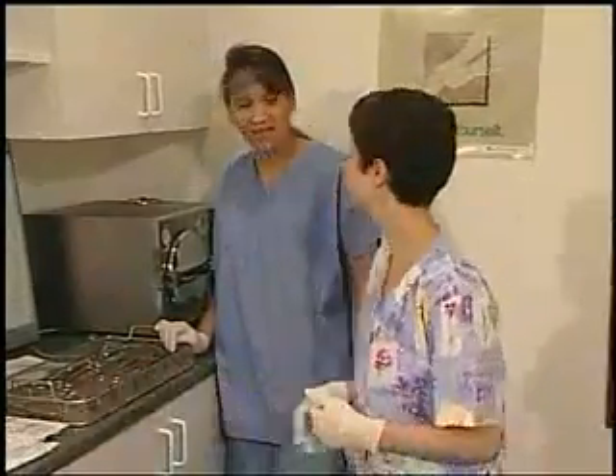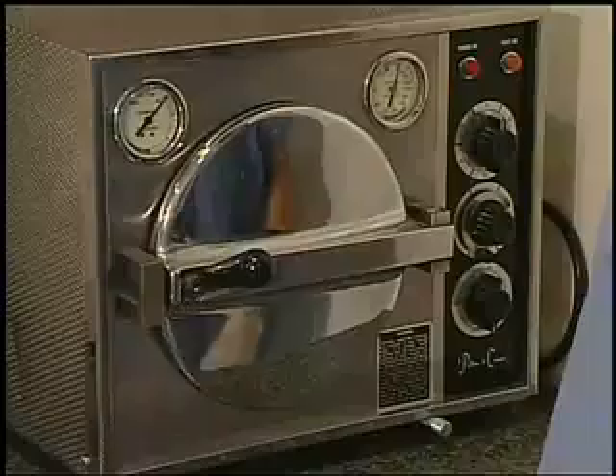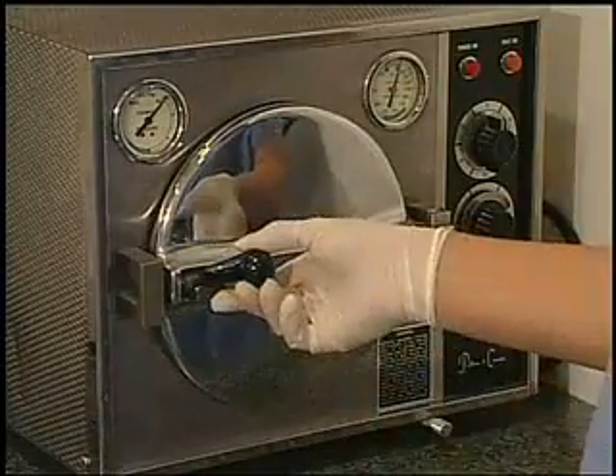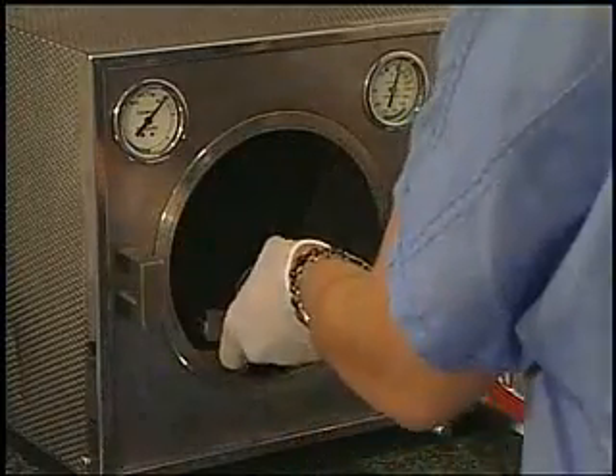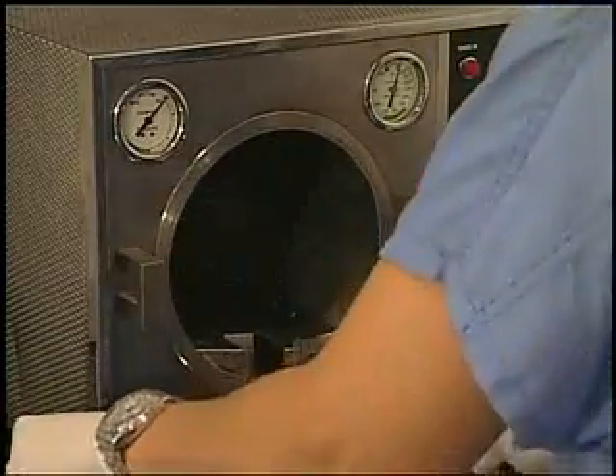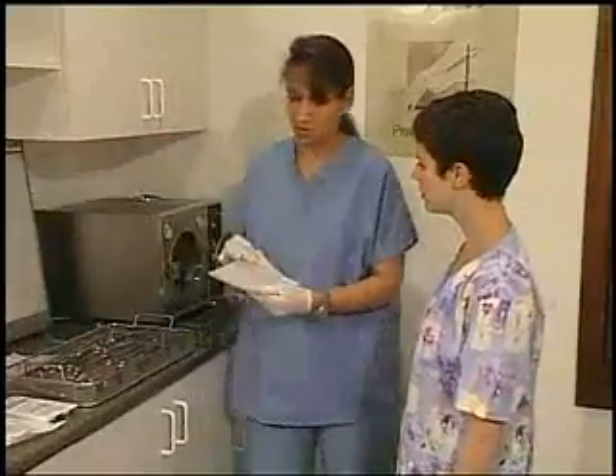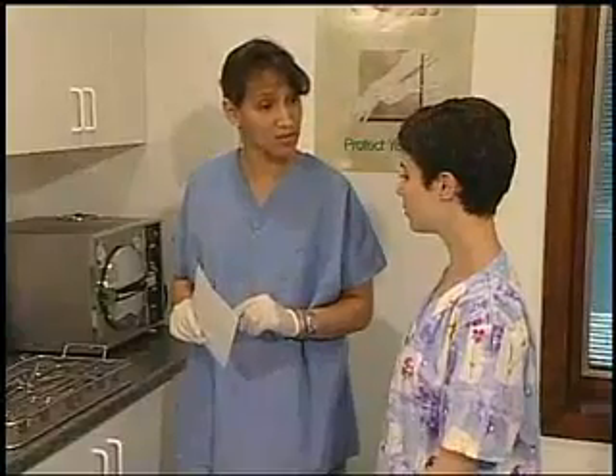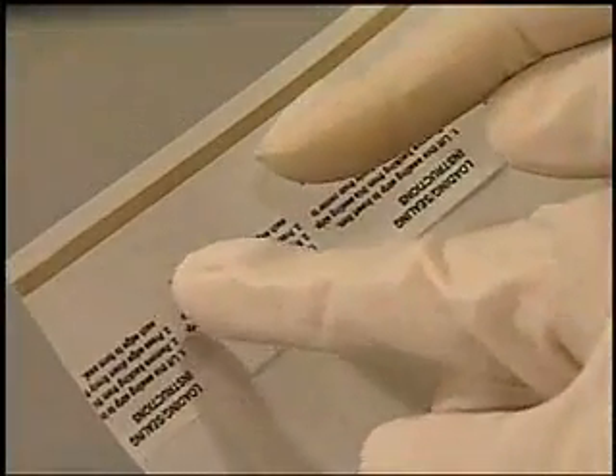Well, wrapping has gotten a lot easier since the advent of the steri pouch. Instruments that are going to be used immediately can just be placed in perforated trays inside the autoclave, unwrapped. But anything that's going to be used for future use usually gets put in a pouch. Usually the sealing strip has a built-in indicator that will change color to show you what's inside has been sterilized. Is this where you put the date? That's where I like to put it.